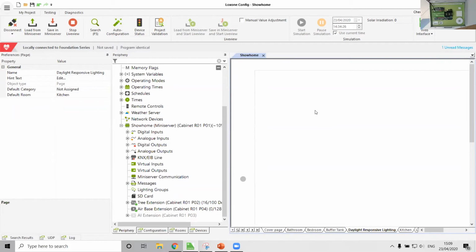And that's still fine to use, but what you need to do is set this up once the building's been finished, because the level of reflection and refraction is going to be based on the objects in the room. So wait until they furnish the office out, get yourself a little motion sensor Air or something that you keep in your van and temporarily connect it to the system, stick that on the desk to measure when you're at 600 lux and compare that against what the one on the ceiling says. So if the one on the ceiling says 200 when this one's reading 600, you know that 200 lux on the ceiling equals 600 lux down here.